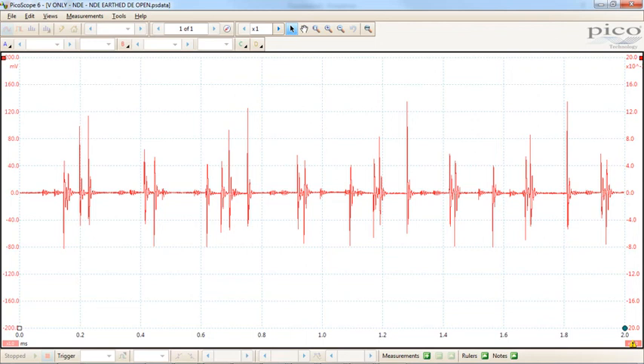So that's a microfiber brush, which is not generally considered to be as low resistance as, let's say, a bristle type brush or a silver graphite brush in good condition on a clean installation. So it's very effective, and it brings your voltage down by a massive amount, like sort of 50 times.